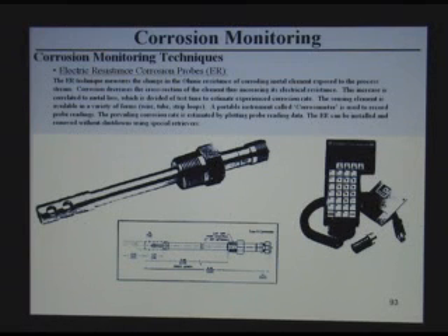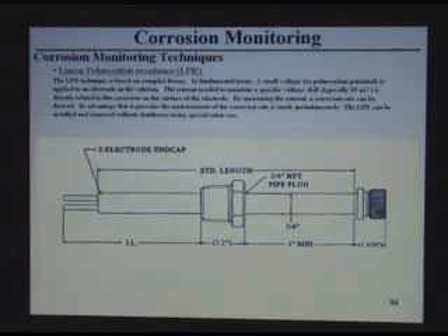This one is called the electric resistance probe. There's another one called the linear polarization probe. It's similar, with two electrodes like that, carrying a certain voltage. If corrosion happens, this voltage changes, and from that it's correlated to the corrosion rate, which can also be measured here.